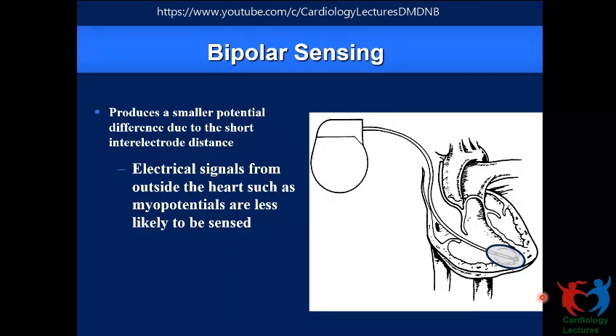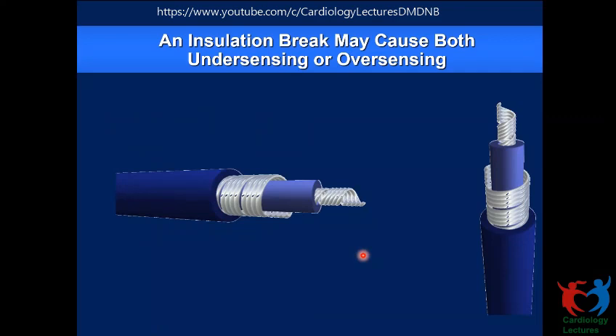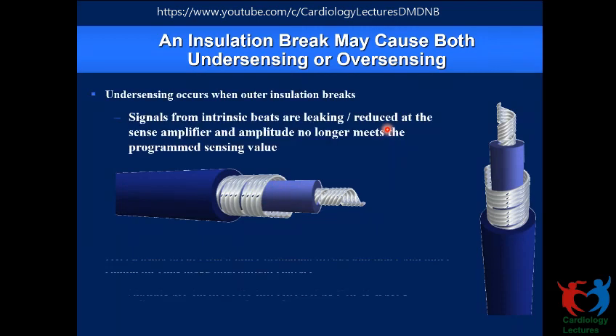So that's one aspect. The insulation break and also the conductor fracture can cause oversensing and undersensing. If you're looking at a bipolar lead, there can be two forms of insulation break: an outer insulation break and an inner insulation break. If there is an outer insulation break, then the R wave amplitude that's coming into the pacing system through the conductor wires can seep out, and the amplitude that is seen by the pacemaker might become lesser. So that might cause undersensing. Let's say there is a fracture or inner insulation erosion. This might result in contact of the anode and the cathode that can cause short circuiting, and it can also generate an electrical impulse like a make-break signal that might result in oversensing. So both of these can cause oversensing and undersensing.